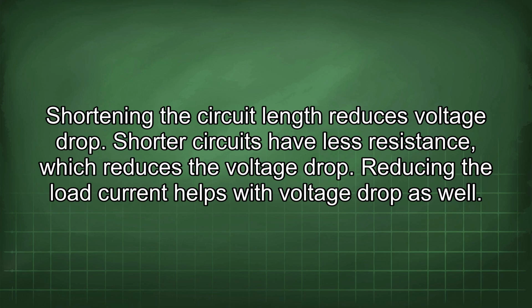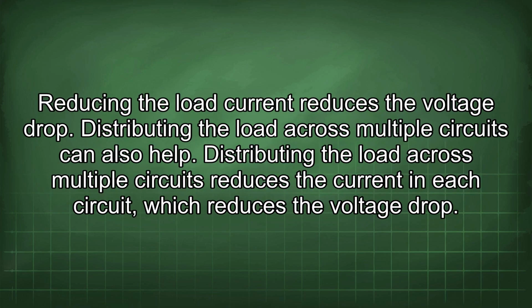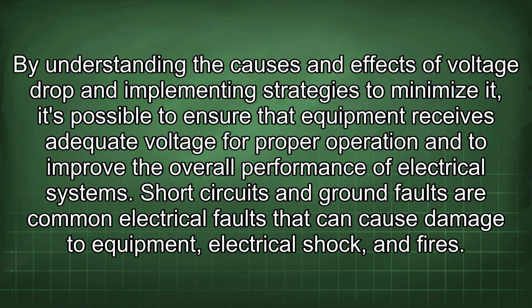Reducing the load current helps with voltage drop as well. Reducing the load current reduces the voltage drop. Distributing the load across multiple circuits can also help. Distributing the load across multiple circuits reduces the current in each circuit, which reduces the voltage drop. By understanding the causes and effects of voltage drop and implementing strategies to minimize it, it's possible to ensure that equipment receives adequate voltage for proper operation and to improve the overall performance of electrical systems.